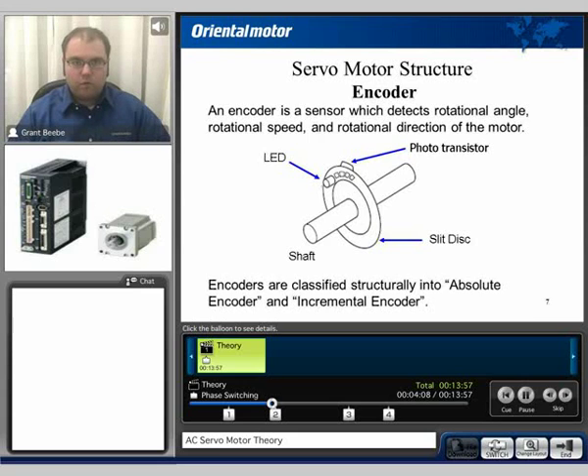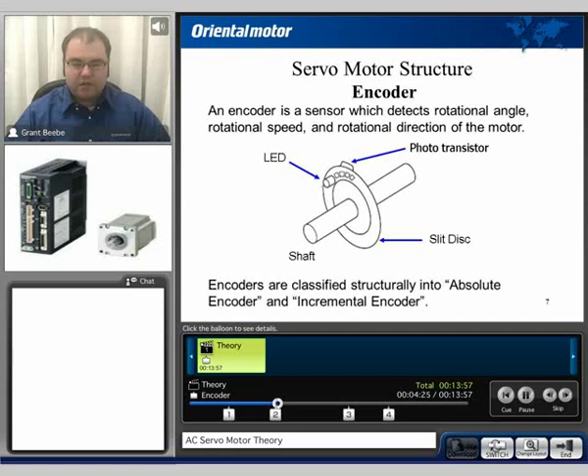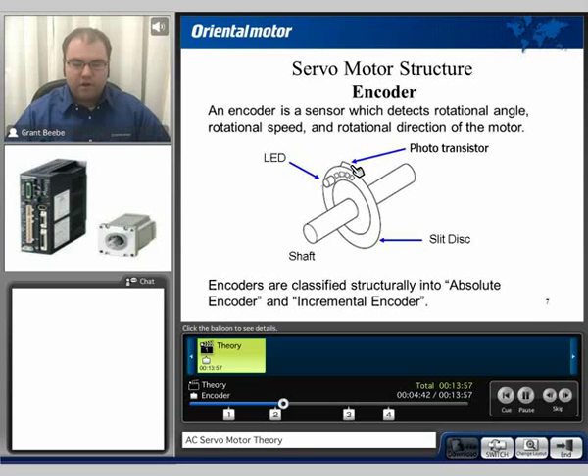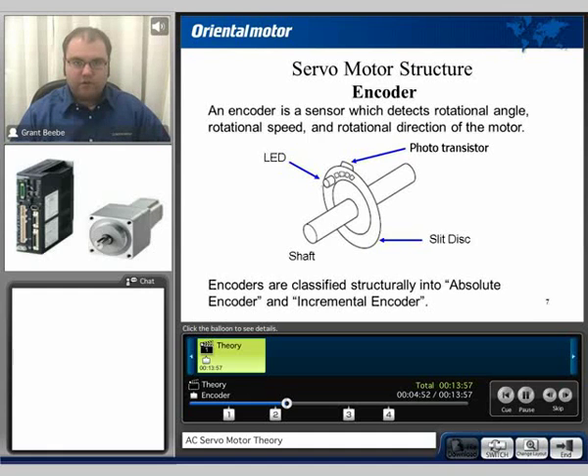Going back to what really makes a servo motor a servo motor is the inclusion of the encoder. An encoder is a sensor which detects the rotational angle, the rotational speed, and the rotational direction of the motor. Basically it's an optical slit disk mounted onto the shaft, and through an LED and a photo transistor it keeps track of the actual rotation angle of that shaft. When the LED light transfers through the slit disk, it activates the photo transistor — every time one of these openings passes, the photo transistor is activated. Encoders are classified into two types: either an incremental type encoder or an absolute encoder.